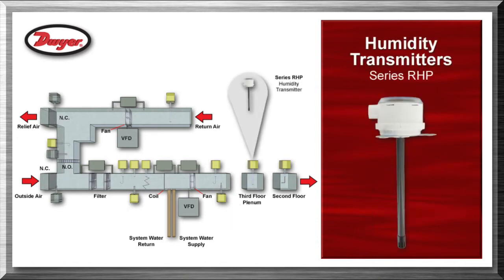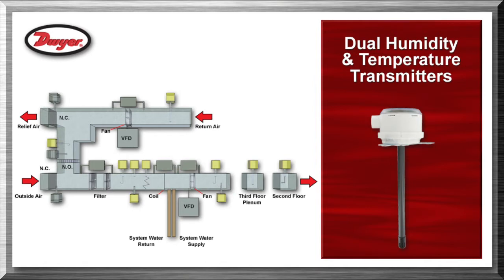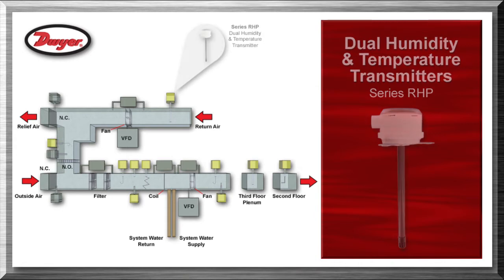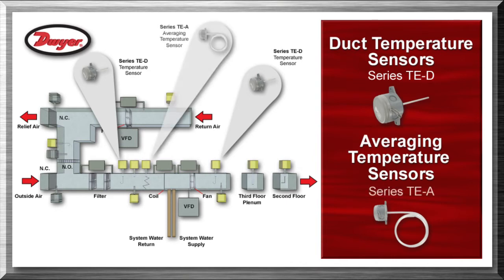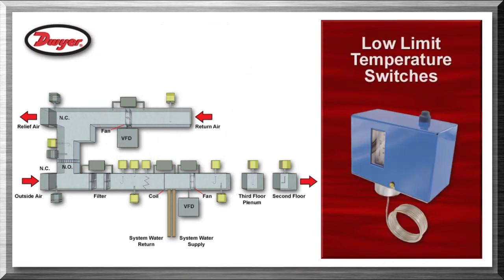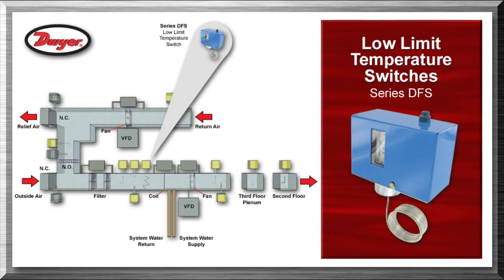Humidity transmitters series RHP are inserted into the duct and used to monitor discharge humidity in systems with enthalpy wheels or humidifiers. Dual humidity and temperature transmitters series RHP are inserted into the duct and used to monitor exhaust air humidity and temperature for economizer applications. Duct temperature sensors series TE-D and averaging temperature sensors series TE-A are inserted into the duct and used to monitor the supply air, mix air, and exhaust air temperatures. Low limit temperature switches series DFS are inserted into the duct to monitor temperature to prevent frost buildup on the coils, protecting the coils from freezing.